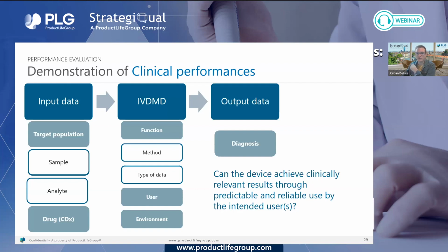Indicators of clinical performance vary and depend strongly on the intended purpose and performance claims. The IVDR sets out that clinical performance may not be required for certain devices in Article 2.39. For example, clinical performance data may not be expected for non-sterile specimen receptacles, microscopic glass slides, or some general reagents. In such cases, and where due justification is given, a clinical performance report would not be expected.